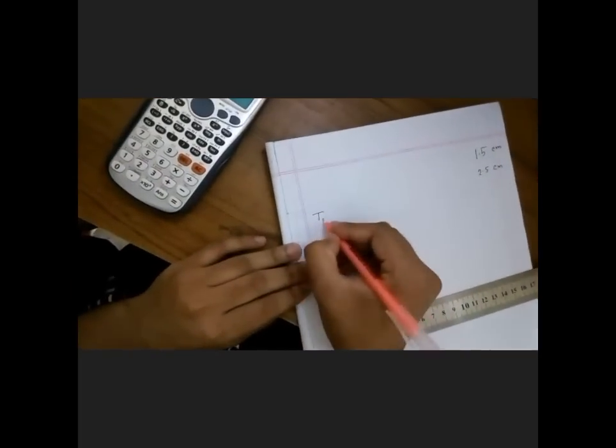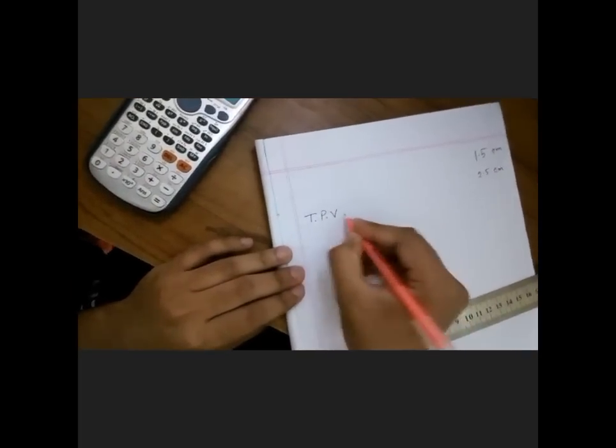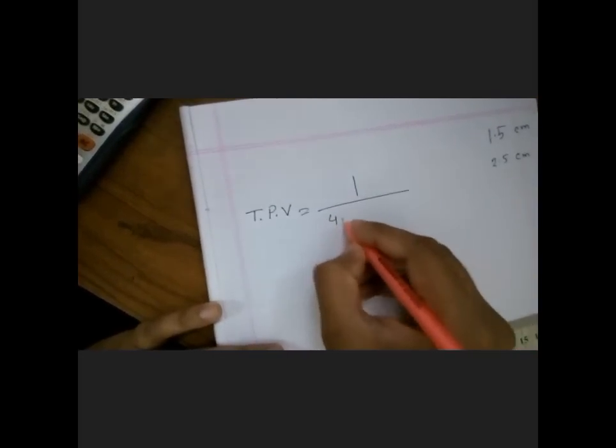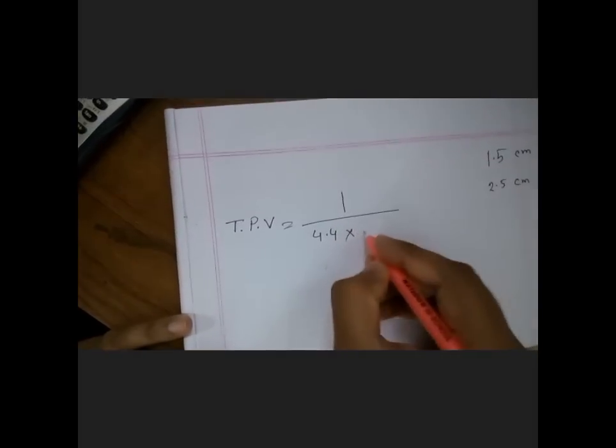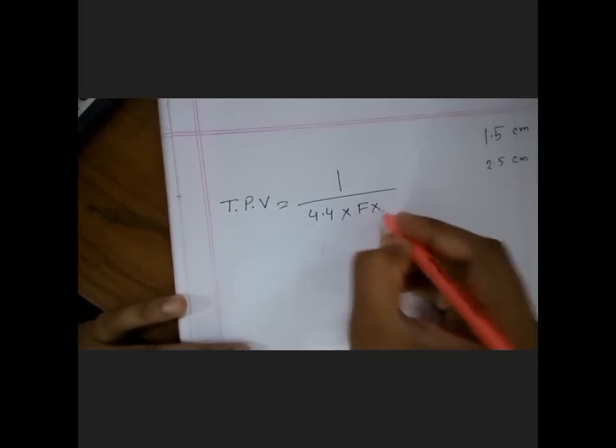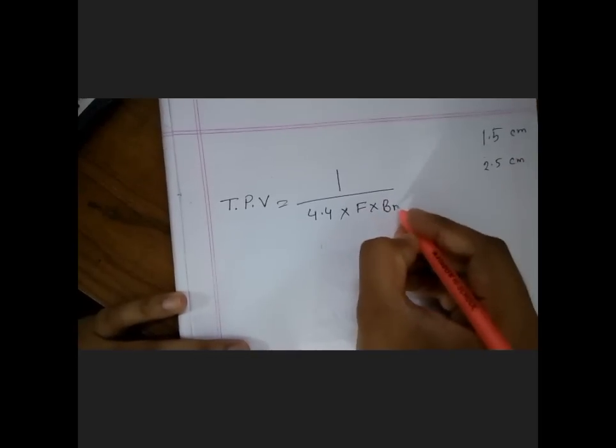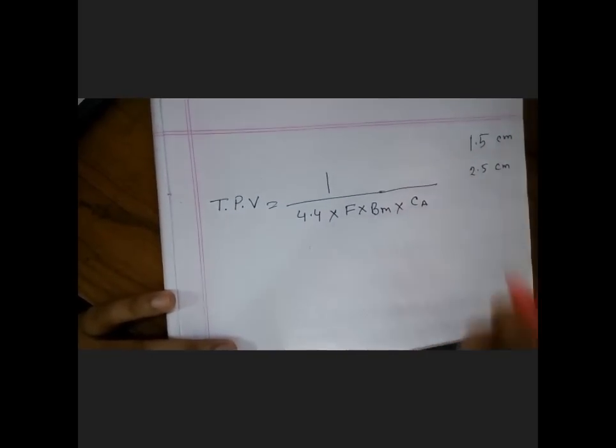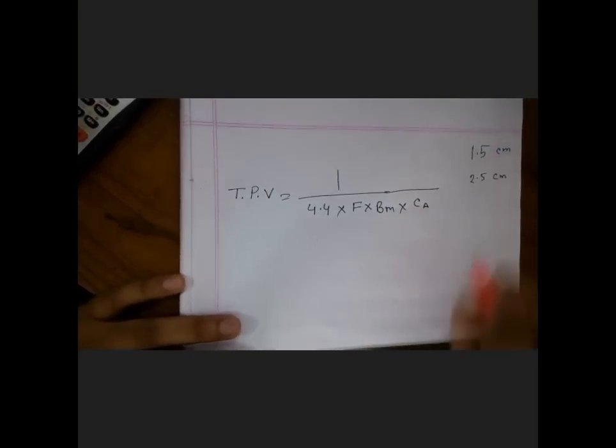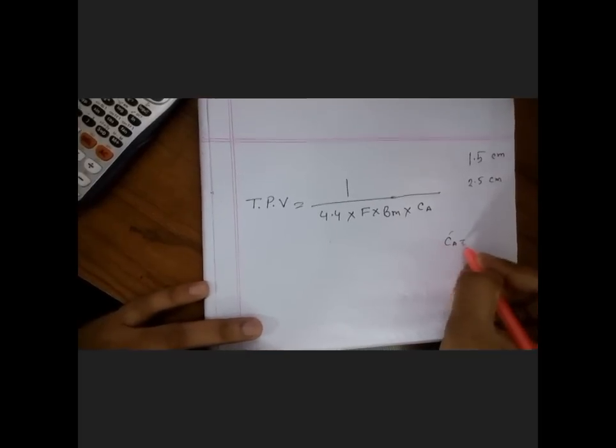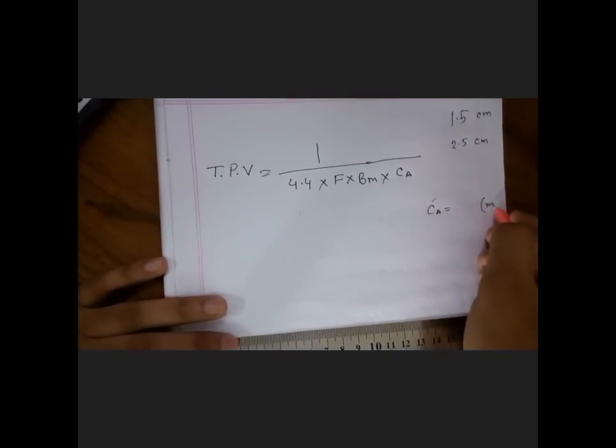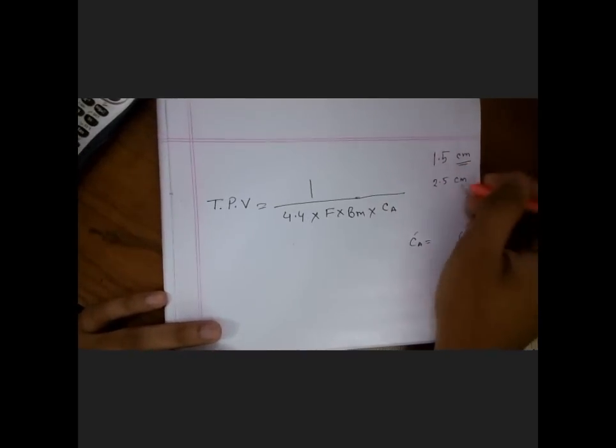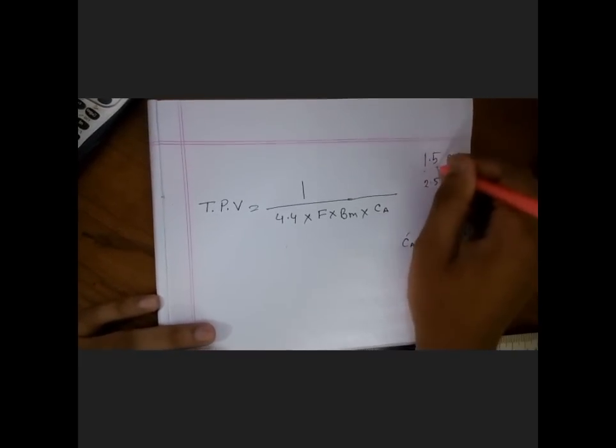And the law is, I'll write here: turns per volt equal to 1 by 4.4 into F into BM into core area. Remember the core area should be taken into meters square. Remember it's meters, but we are taking centimeters, so we should convert this into meter.